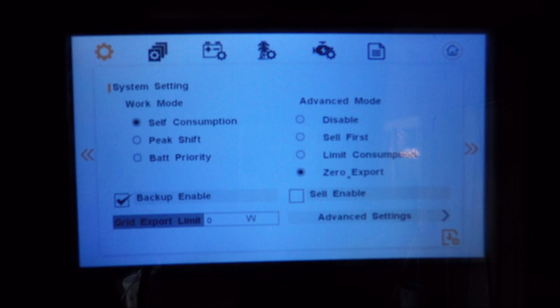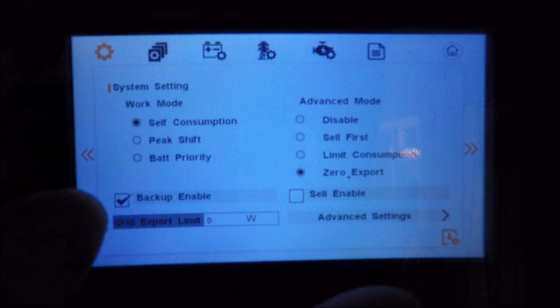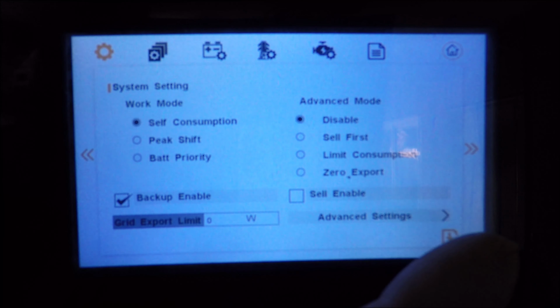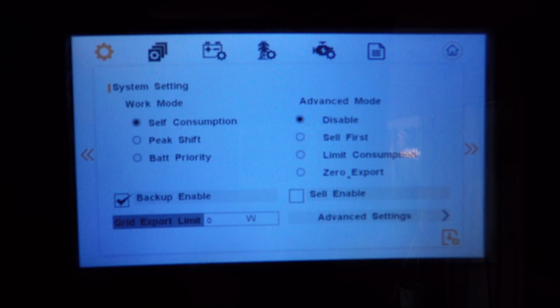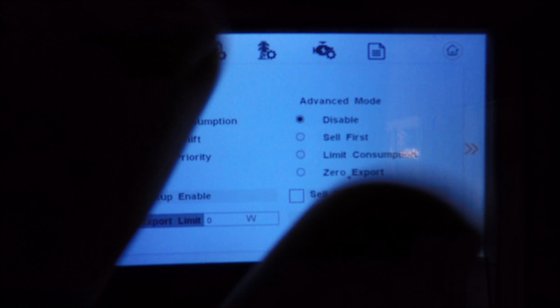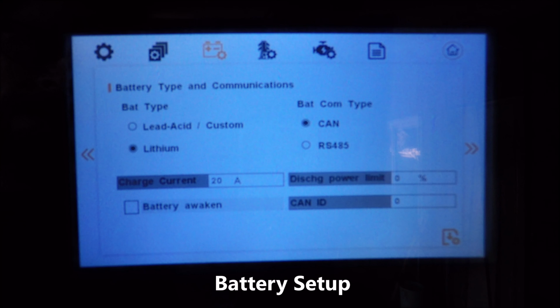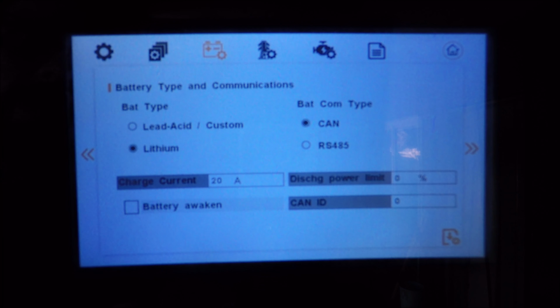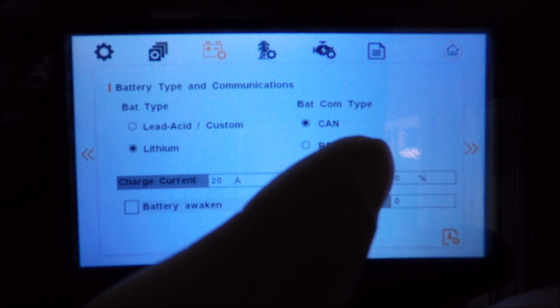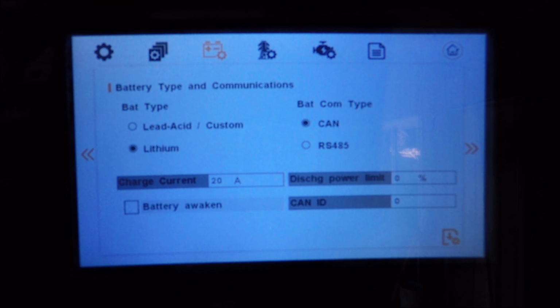When going through the setup process, after you have set your system settings of how you want the inverter to work, we're going to go back and save this so that we're set up in basically an off-grid mode. The next step is to set up your batteries. We're going to go to battery, and we have 2 battery types. By default, the system will default to lithium. You have 2 types of communication, CAN and RS485. The inverter seems to like the CAN setting better than the RS485 setting.